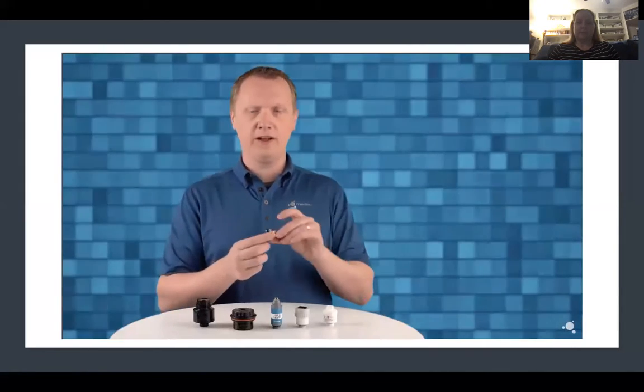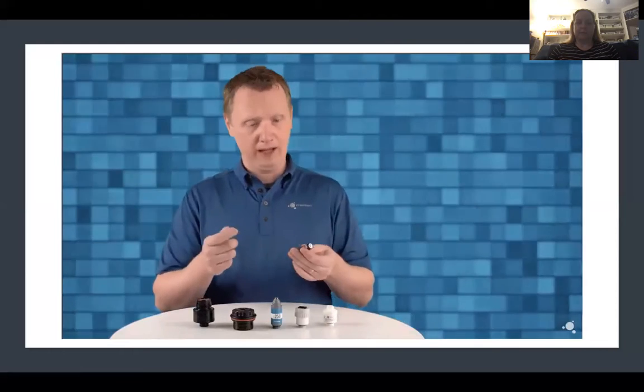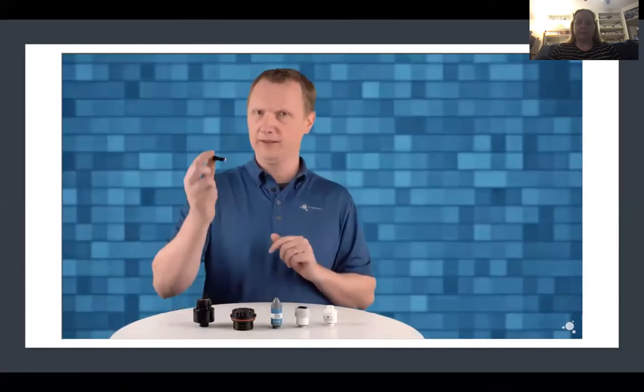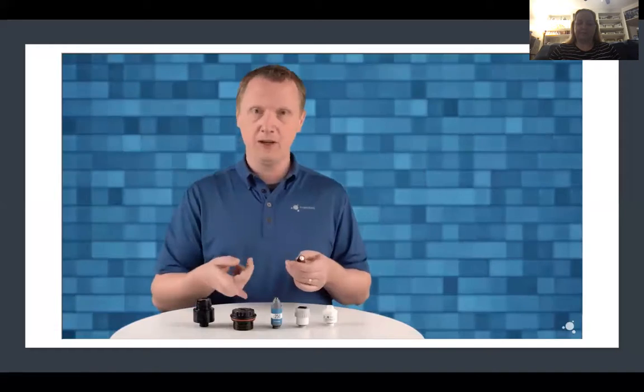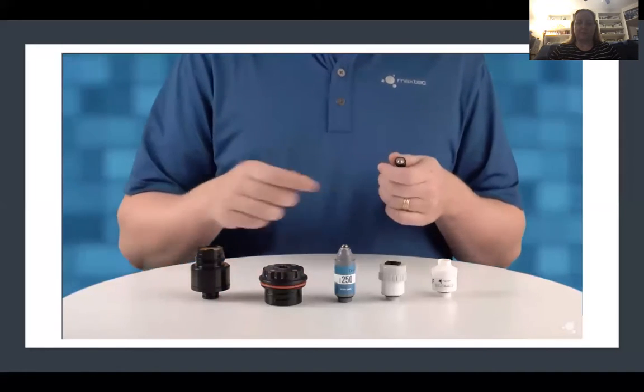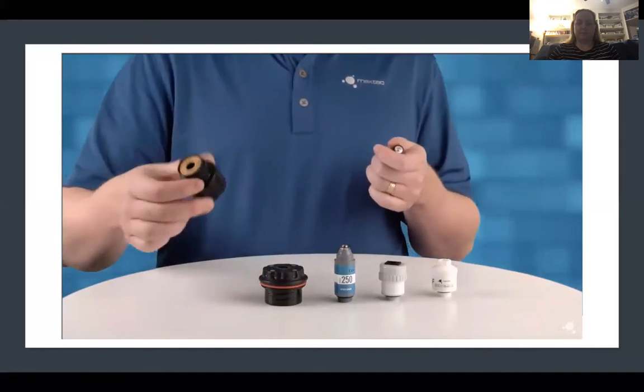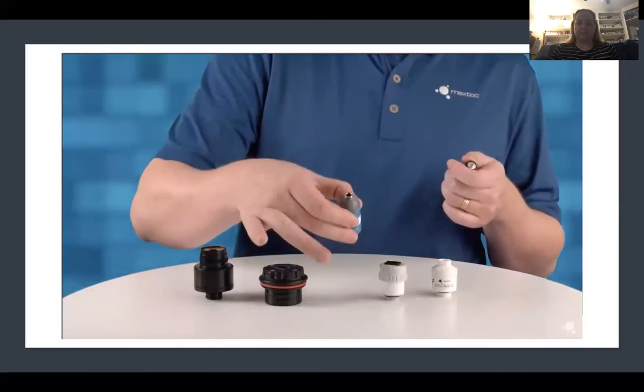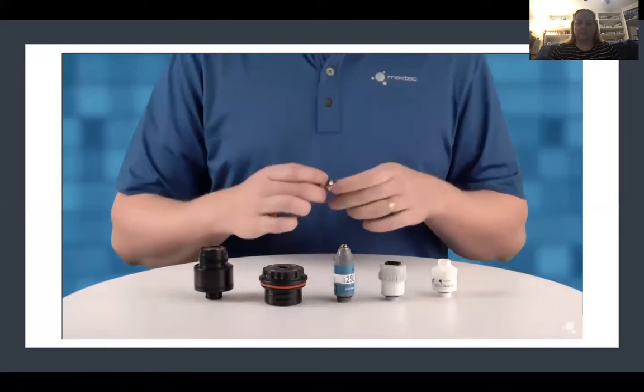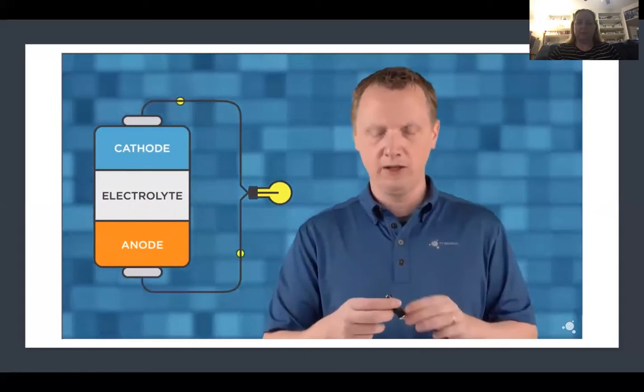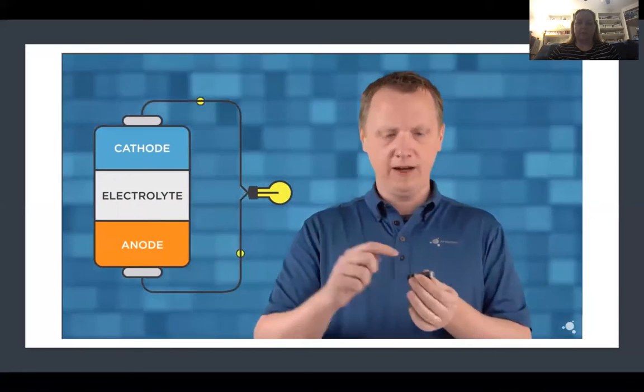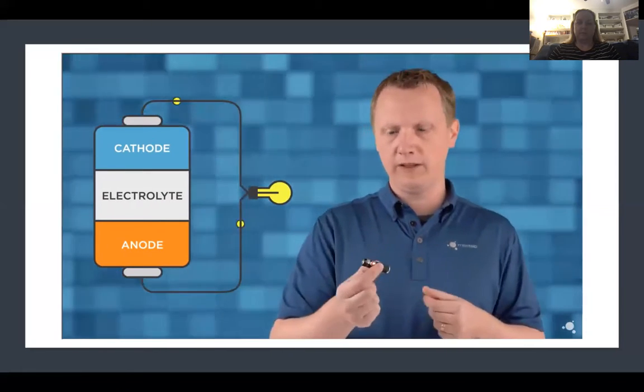Let's take a look. So to help us better understand oxygen sensors, it's actually helpful to talk about batteries for just a second. Like batteries, they come in all different shapes and sizes. So we've got little batteries and big batteries for different applications. There's different sizes of oxygen sensors for different applications. They have different forms to fit in different types of devices. They have different types of connectors depending on what they're being installed in. And if we look at the inside of a battery, there is a cathode and an anode inside of electrolyte. And what that's allowing to happen is electrons are flowing from the anode to the cathode. And when this is connected to a device, it completes that circuit and allows for the flow of electrons.